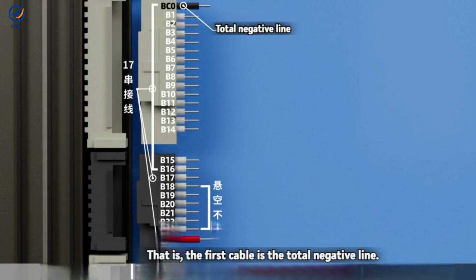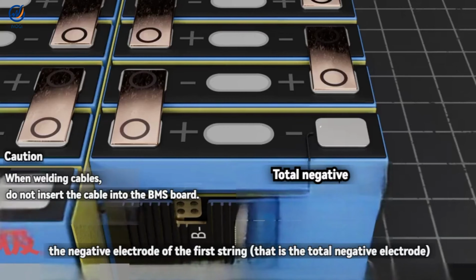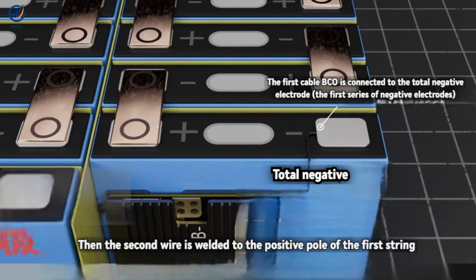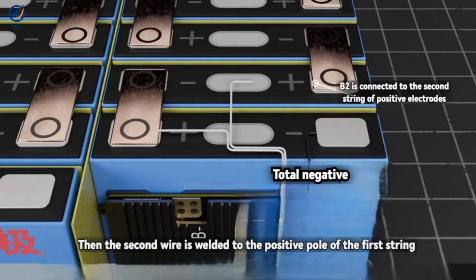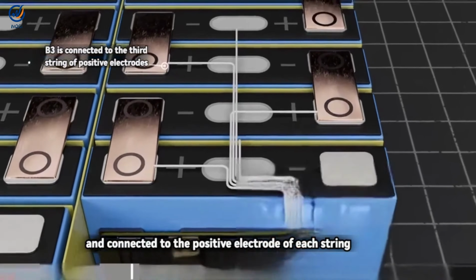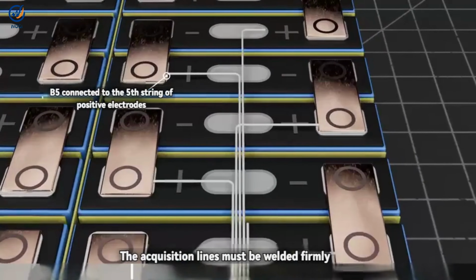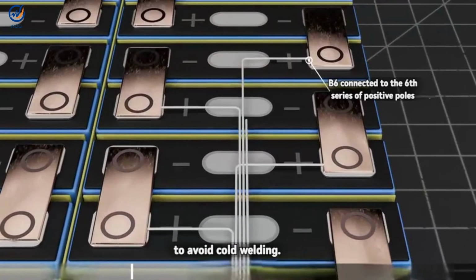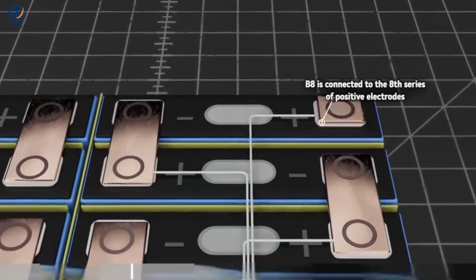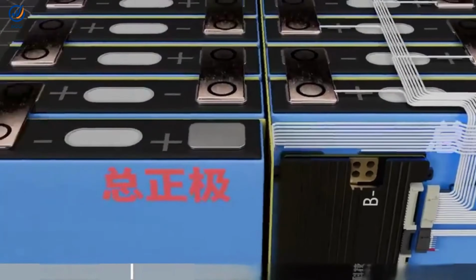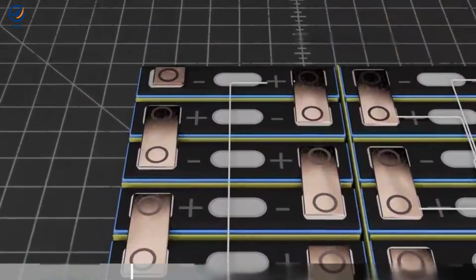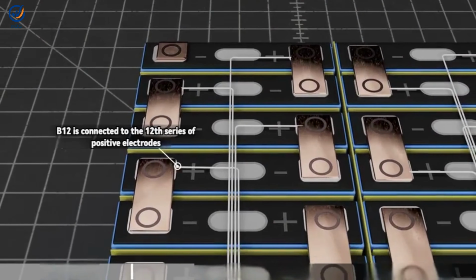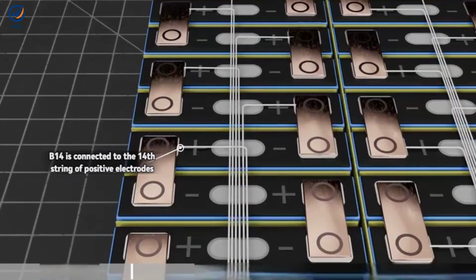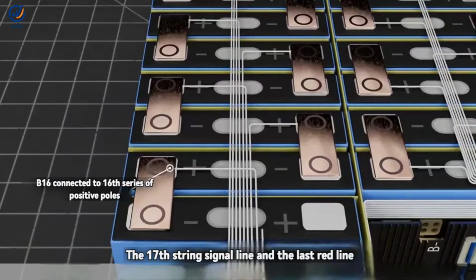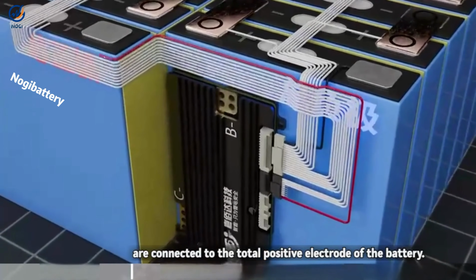That is, the first cable is the total negative line. The first cable is welded to the negative electrode of the first string, that is, the total negative electrode. Then the second wire is welded to the positive pole of the first string, and so on, connected to the positive electrode of each string. The acquisition lines must be welded firmly to avoid cold welding. The 17-string signal line and the last red line are connected to the total positive electrode of the battery.